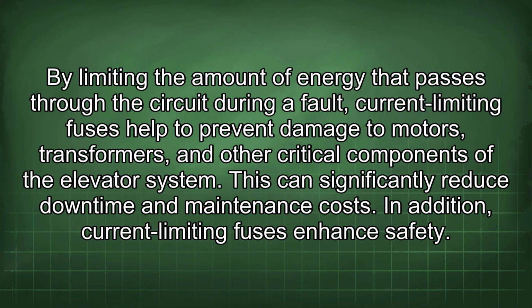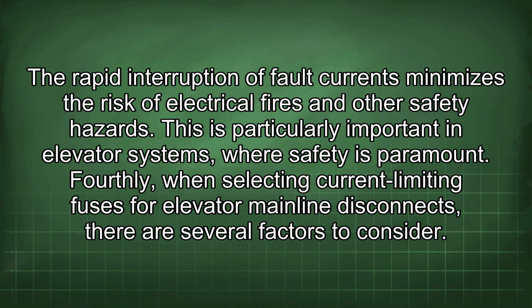By limiting the amount of energy that passes through the circuit during a fault, current-limiting fuses help to prevent damage to motors, transformers, and other critical components of the elevator system. This can significantly reduce downtime and maintenance costs. In addition, current-limiting fuses enhance safety. The rapid interruption of fault currents minimizes the risk of electrical fires and other safety hazards. This is particularly important in elevator systems where safety is paramount.